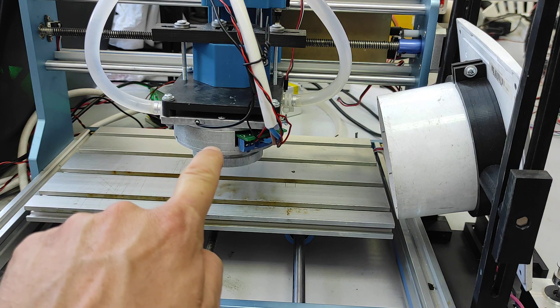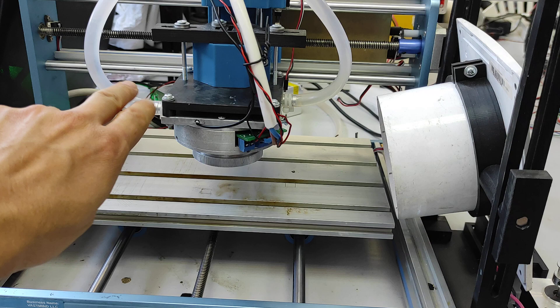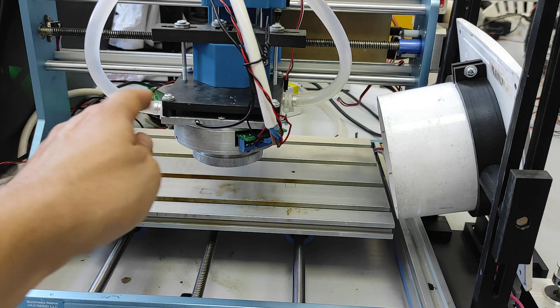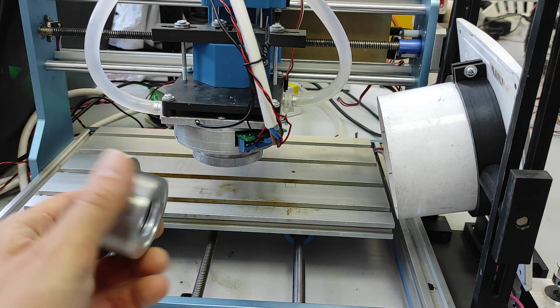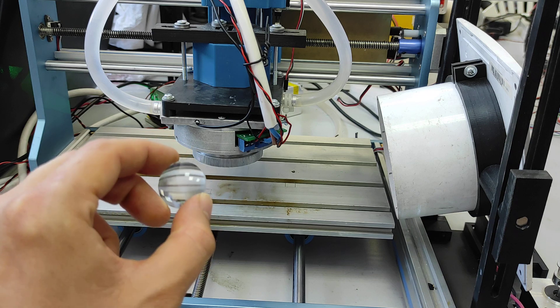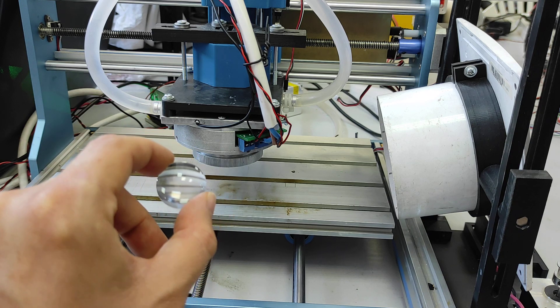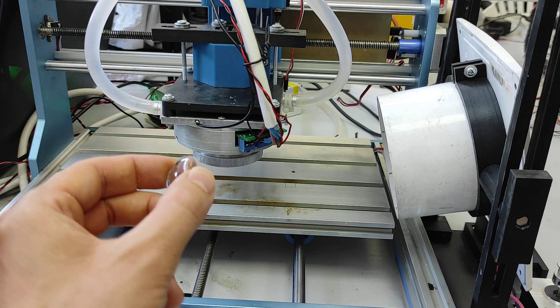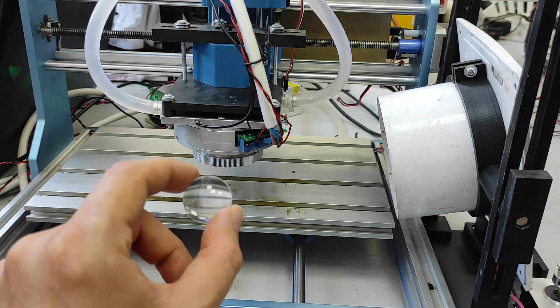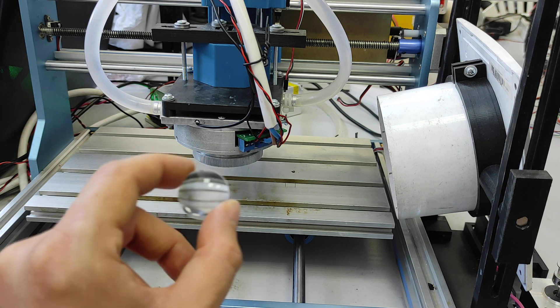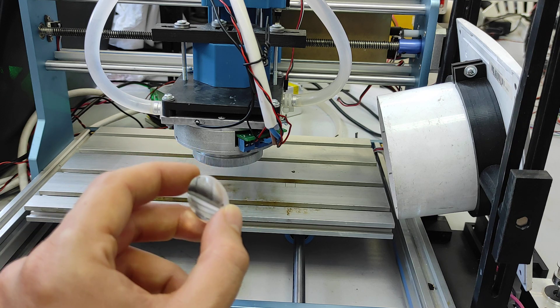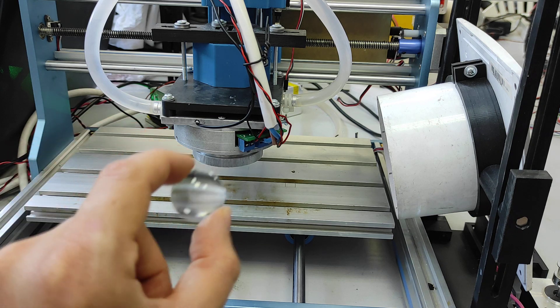This laser diode array is inside. We have a water cooling system over here and we have our optics. This is our own optical system that we made for this particular laser and we're using quartz lenses. The problem with regular glass BK7 or K8 glass is that it absorbs a lot of energy, a lot of power, and then the laser lens can be damaged.